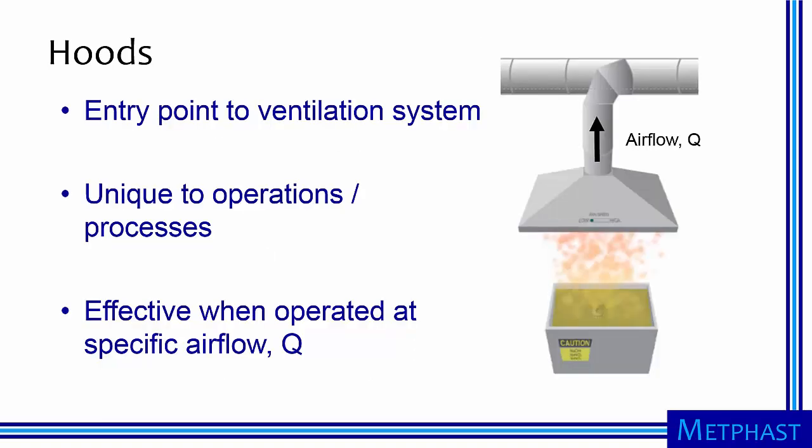Hoods are the entry point to the ventilation system. They have unique designs to serve a given operation or process. For example, we show a canopy hood used to ventilate hot vapor from a dip tank. Hoods are effective when operated at a specific air flow rate, commonly abbreviated with the symbol Q, and measured in the duct just downstream of the hood.